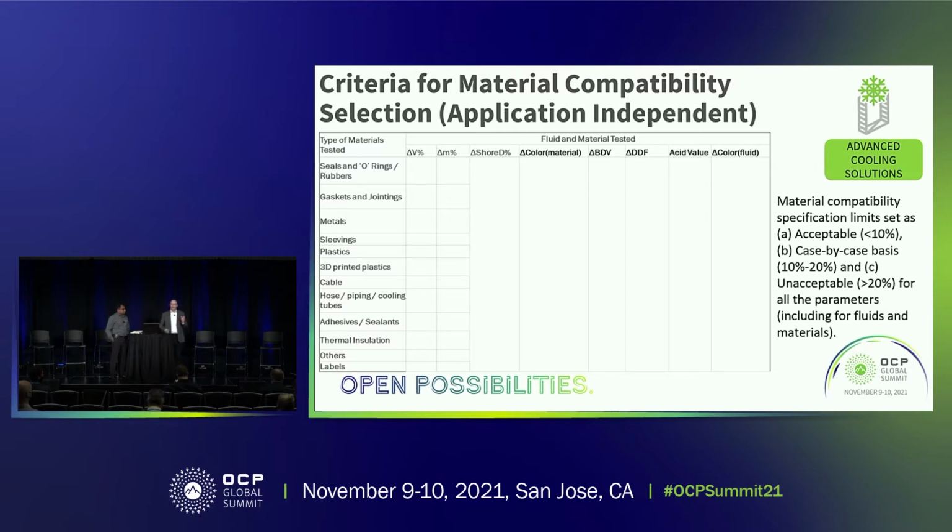Number one, even though we have the 6 different basic categories of fluids, there are all kinds of formulations within each one of those fluids. So everything needs to be taken with a grain of salt, because a specific fluid within any given category will be slightly different, and maybe significantly different, than a cousin within that same fluid. Similarly, the materials within the server are not all of identical formulation either. So we took a rather generic high-level approach, and because of that, we thought it would be inappropriate to dive into too detailed an assessment within this matrix and maybe mislead people. So we said we're going to do this green, yellow, red light.